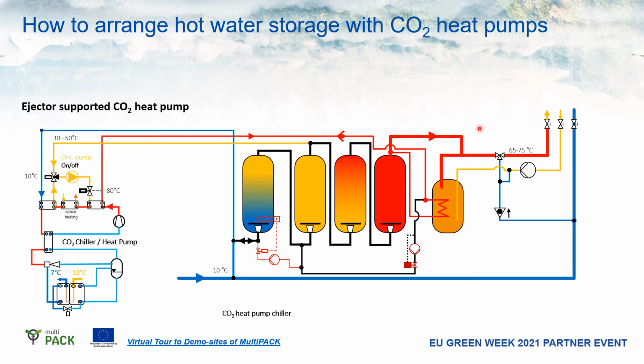In the next slide, I show you another option where we now introduce the novel heat pump chiller from the MultiPACK project, utilizing an ejector to have two temperature levels in the evaporators. And in this case, I also introduced a space heating heat exchanger in case this is needed. So that could be one option, even in between these two other heat exchangers, utilizing reheating and enabling an efficient reheating of cold, relatively warm water. We can also utilize even more of the heat in a dedicated space heating gas cooler. And in this way, we can connect the chiller heat pump to the storage system, distributing hot and cold water to the building while the hot water is circulated.